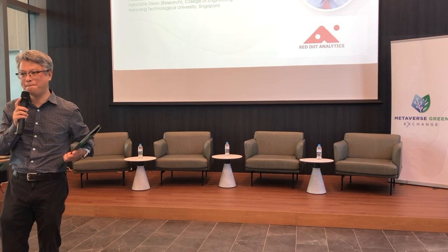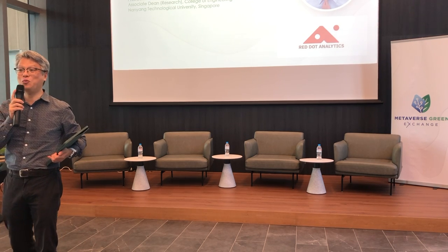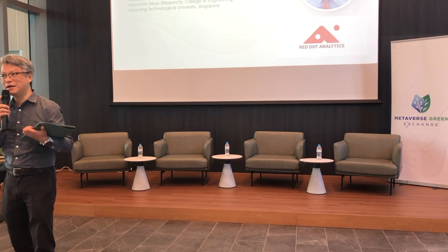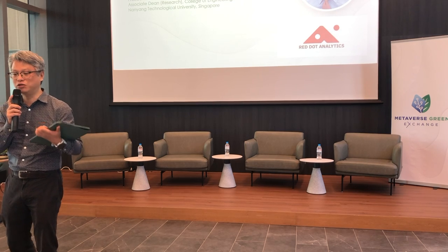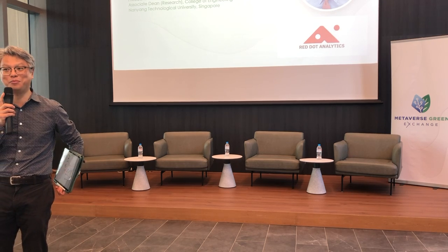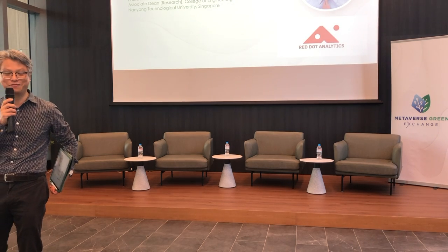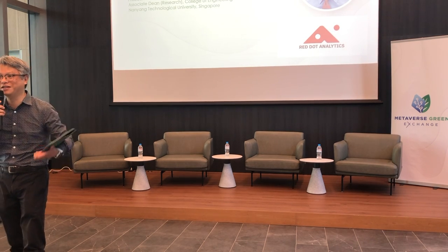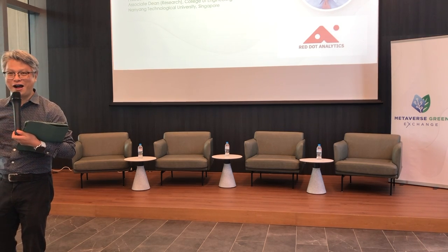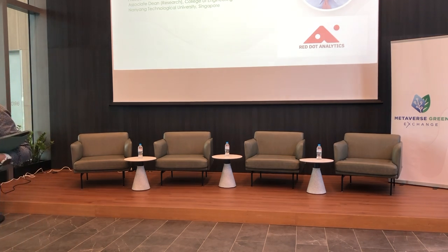But in order to do so, you will need a lot of data to understand and to predict what your IT load may be. Then you pre-cool or you pre-configure the mechanical systems, so that the mechanical system responds to your IT system dynamics. That's a really difficult problem. Mechanical systems have very long time constants, in terms of minutes. IT systems have time constants of less than a second. It's like trying to ask a gorilla to do stitching. That's very difficult, right?